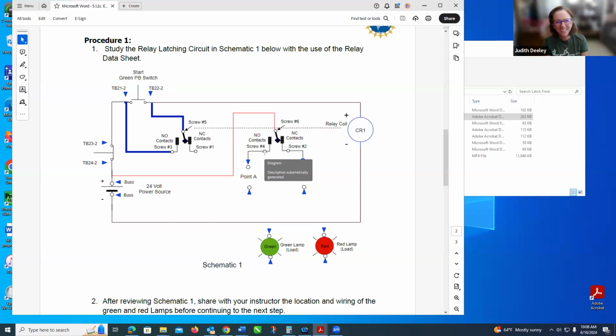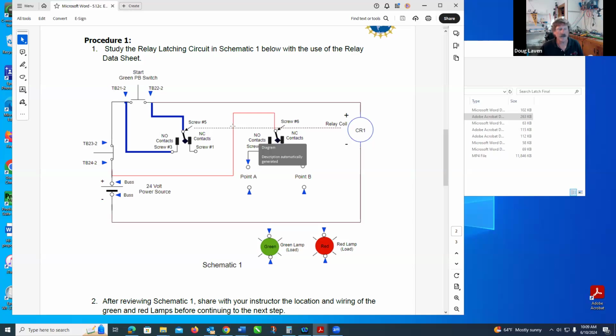Now the people in the apartment pay every other day, so they only pay 15 days out of the month for air conditioning. It switches back and forth. So that's how relays are used. On one side of the relay, I'm tied to the PLC. This side is tied to two 30 amp breakers, 240 volts. But this line here doesn't go back to my low voltage power supply. It ties right up to the 30 amp.